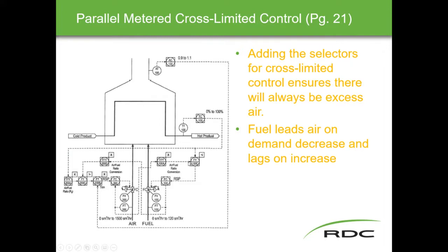What's getting cross-limited here is these two signals. You see this signal coming across from here to here, and this signal coming across from here to here. So this is why we get this cross-limited control. What this does is it ensures that the fuel is going to lead the air on a demand decrease, meaning that the fuel is going to...